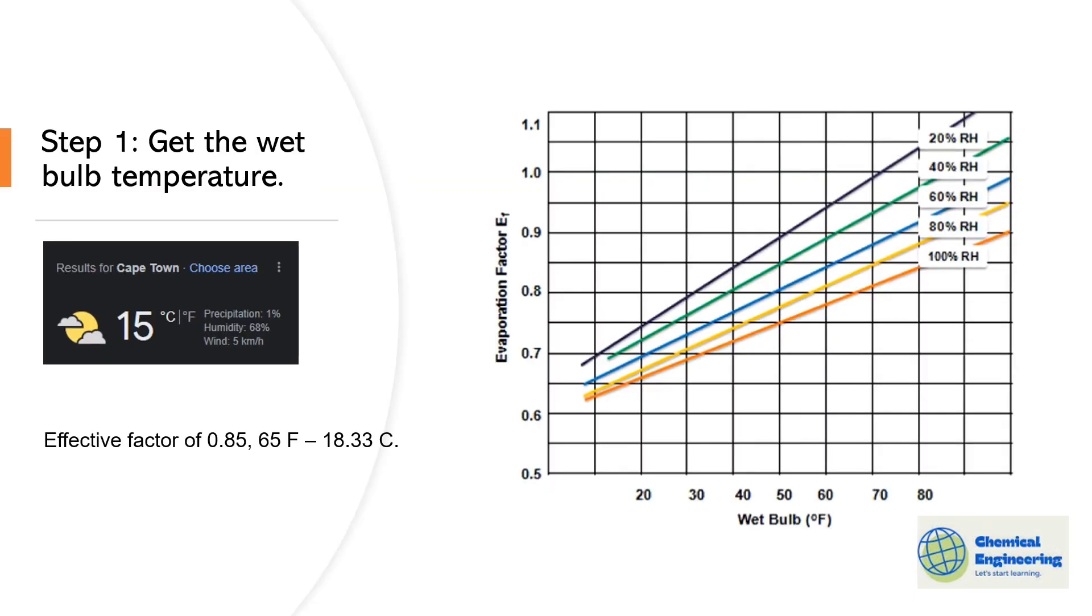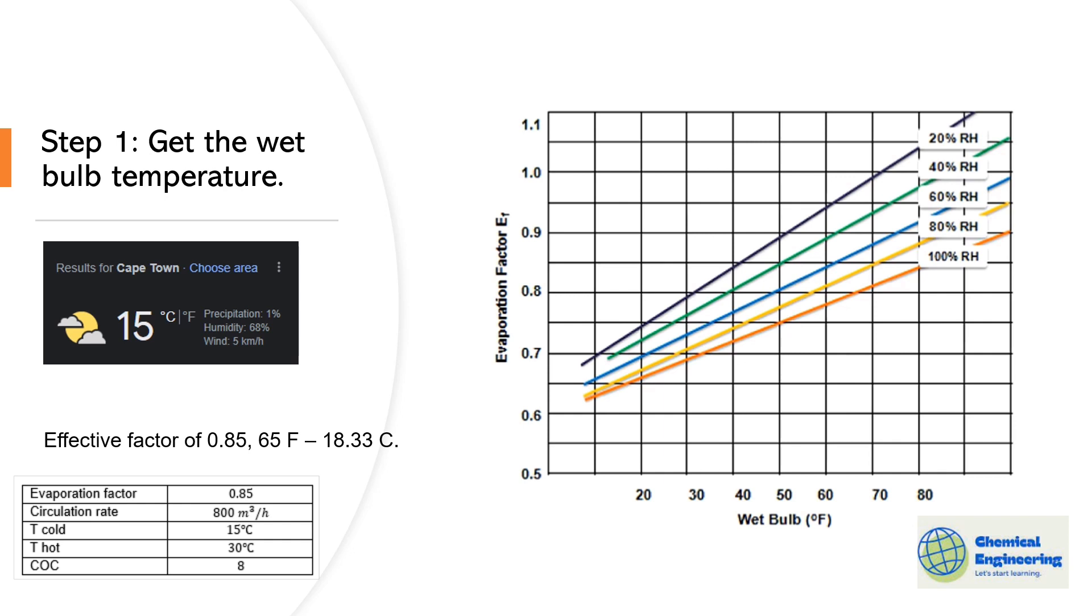Okay now let us be practical. Say we live in a city called Cape Town and the humidity there is roughly around 68. With an estimated evaporation factor of 0.85, relative humidity of roughly 68 percent, we can then assume or go to a graph and get a rough estimate of our wet bulb temperature. If you go on your graph there, you might get 65 fahrenheit which if you convert to degrees celsius can give you 18.33 degrees celsius.